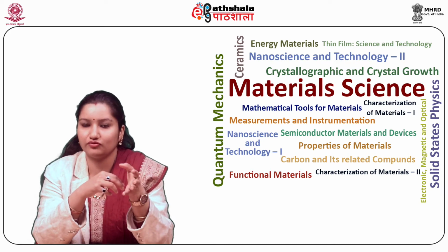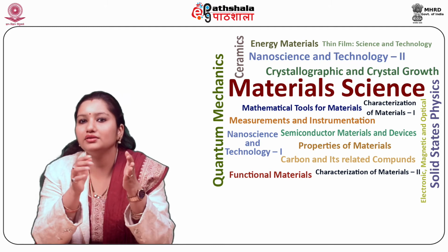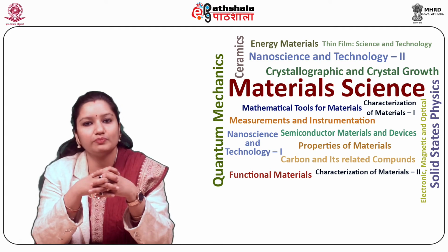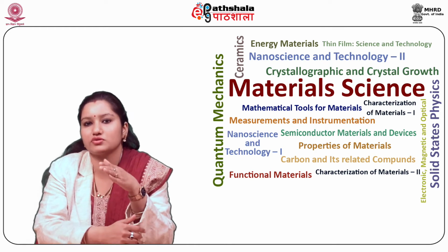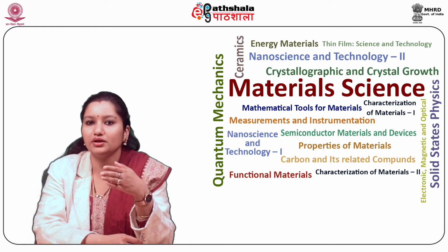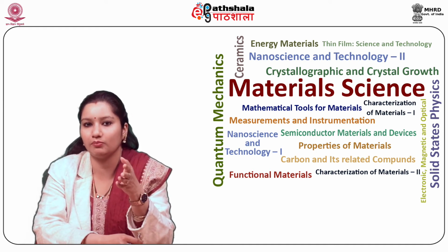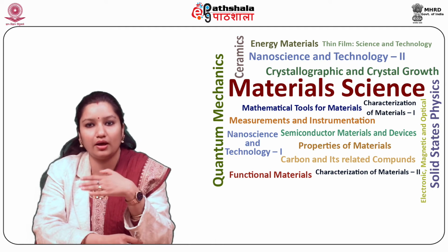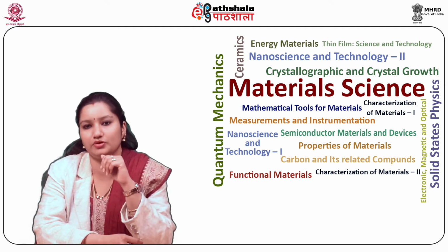A collection of electrons occurs in the space between the filament tip and the cap, which is called a space charge. Those electrons at the bottom of the space charge nearest to the anode can exit the gun area through the small hole, meaning less than 1 mm, in the Wehnelt cap and then move down the column to be later used in imaging.